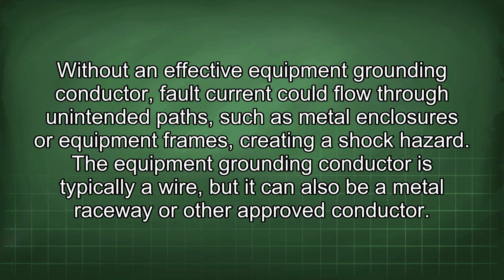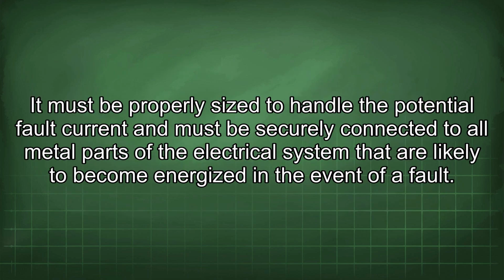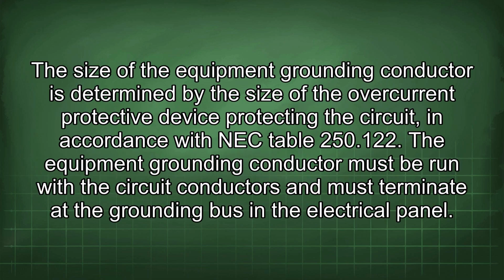The equipment grounding conductor is typically a wire, but it can also be a metal raceway or other approved conductor. It must be properly sized to handle the potential fault current and must be securely connected to all metal parts of the electrical system that are likely to become energized in the event of a fault.